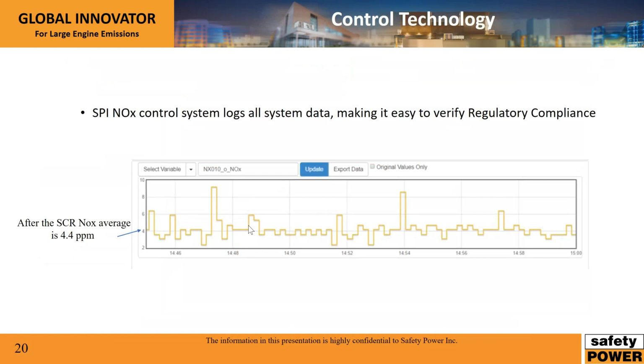So this is basically the result of all our controls. The average NOx out of our system for the same installation during the same period is 4.4 parts per million, which is very, very low. You'll also see some peaks here and there, but they recover very quickly, and that is due to these solid-state sensors.